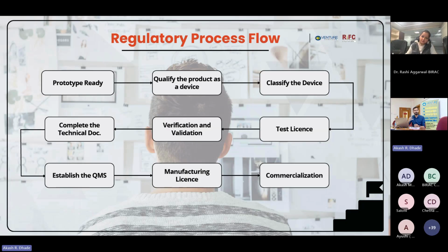So, for example, for biocompatibility, there are standards called as ISO 10993. For EMC testing, there are standards called as IEC 60601. For softwares, there are standards such as IEC 62304. So what you need to do is you have to go through this standard, understand what this standard want, complete the testing as per this standard, and generate this data to submit to CDSCO. Once you complete this verification and validation activities, you compile that data. So you compile V&V data, you compile device description data, you compile your labeling, right?